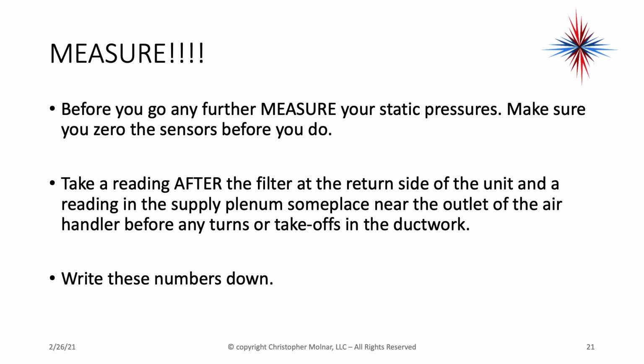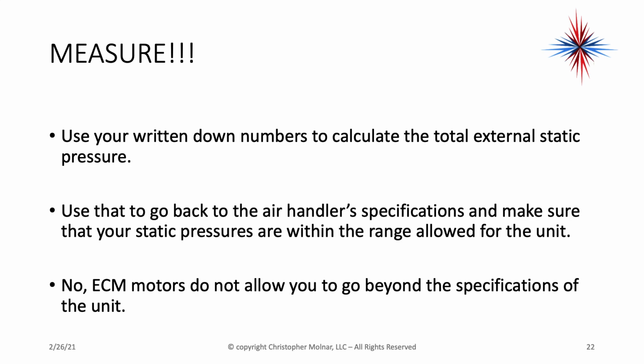Before you go any further, measure your static pressures. Make sure you zero the sensors first. Take a reading after the filter at the return side of the unit, and a reading in the supply plenum someplace near the outlet of the air handler, before any turns or takeoffs in the ductwork. Write these numbers down. Use your written down numbers to calculate the total external static pressure. Use that to go back to the air handler specifications and make sure that your static pressures are within the range allowed for the unit.